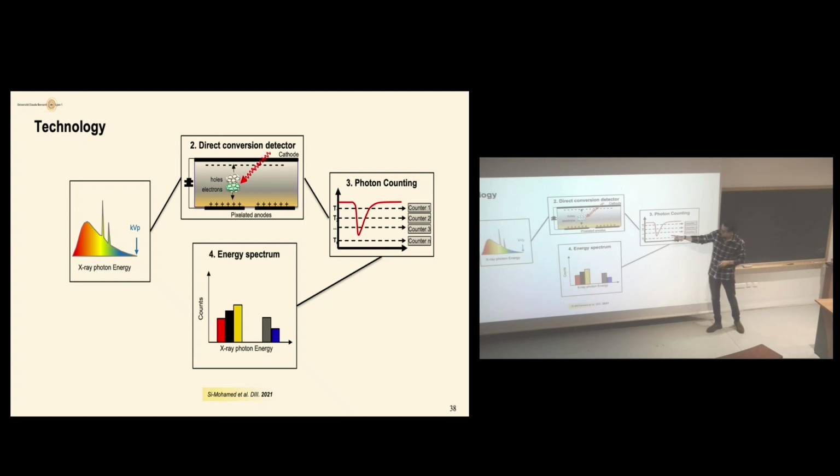So the signal of the photons will be classified into different energy bins. And this is important because energy integrating detectors did not allow any specific energy resolving capabilities. In that setup, each photon from the low to the high energy will be counted, this energy will be compared and put in energy windows.